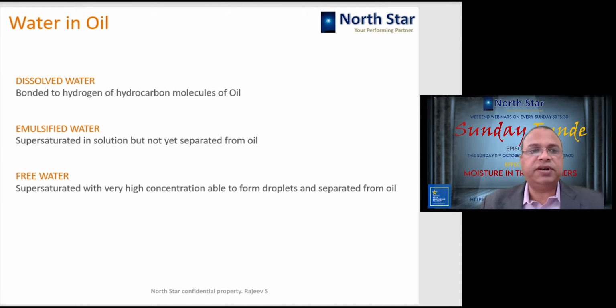Okay. So I will repeat this slide once again. The water in the oil is in three forms: dissolved water, emulsified water, and free water. Dissolved water is typically within the oil and it is bonded with the hydrogen of the hydrocarbon molecules and it is not freely available. Second is emulsified water, which is in semi-suspended form in supersaturated condition, so it is neither removed from the oil nor freely moving in the medium, it is somewhere in between. So that is emulsified water, and this water gives the oil a little milky whitish appearance.